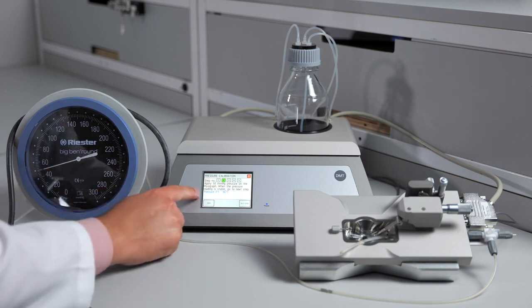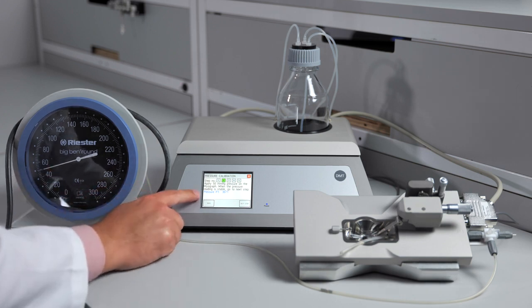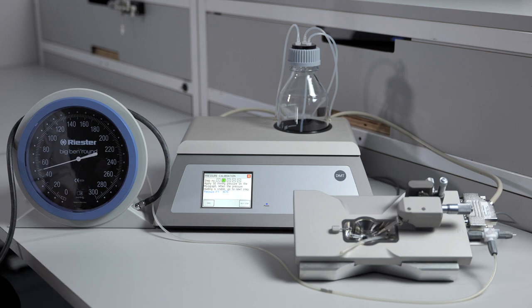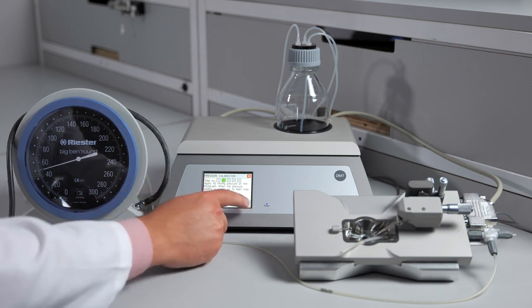You will see that the pressure changed approximately from 3,200 into 3,670. You just want to make sure that the pressure is changing. If the pressure is not changing between each step, you have a block somewhere. The pressure is holding, so we can go to next step.